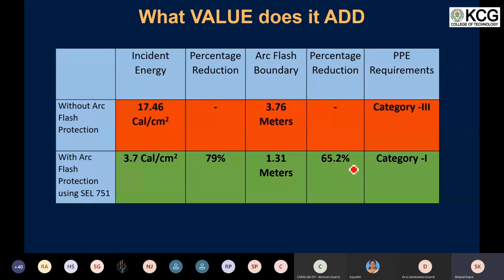That helps not only with the calculation, but even with the PPE that would be required for a person to use in this kind of scenario. If there was no arc flash protection, then the person would require category 3 personal protective equipment. Since they had applied the arc flash protection, now even category 1 PPE is sufficient for working in this kind of environment.